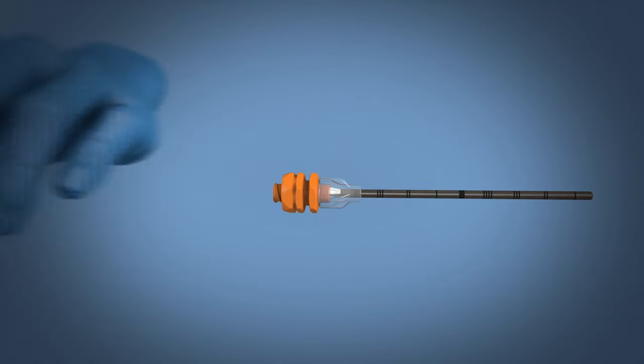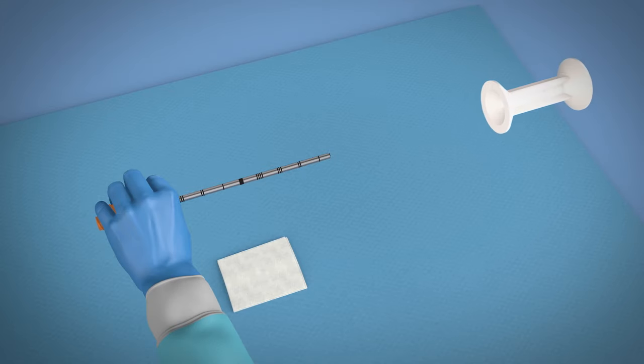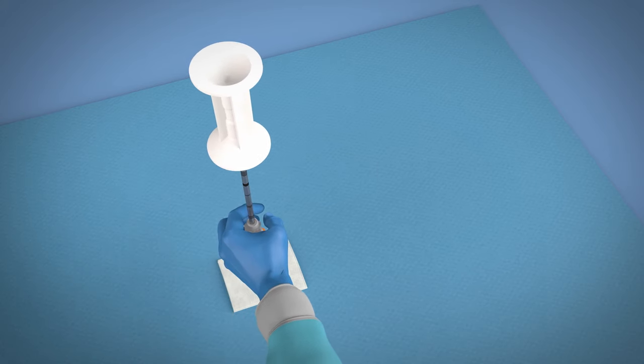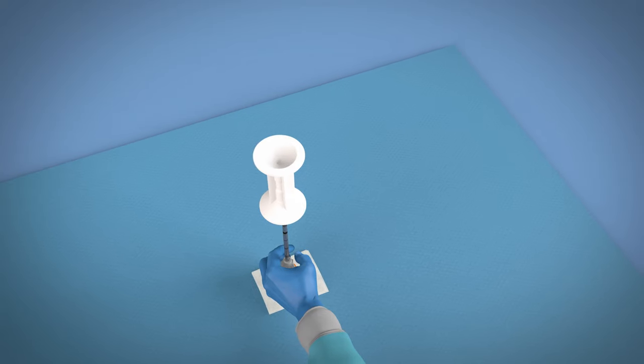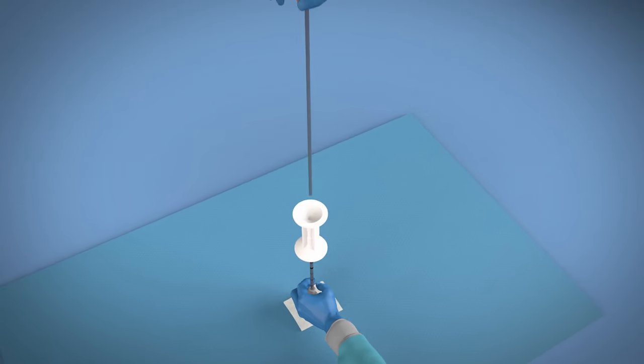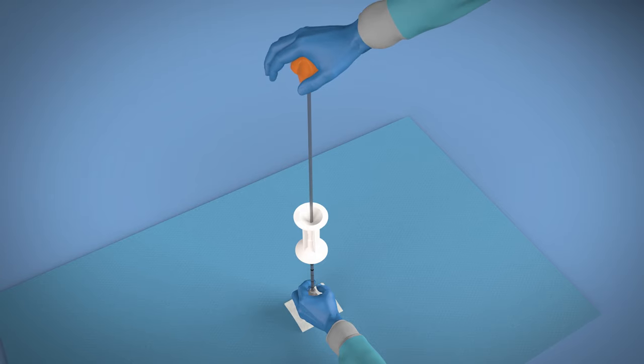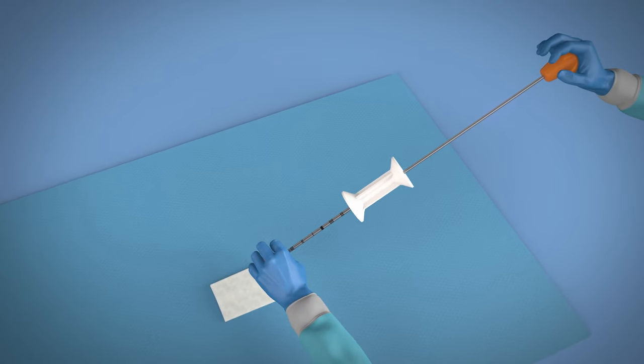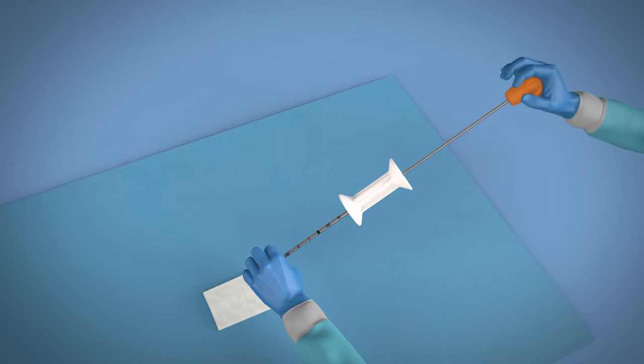Retract the black collar and remove the needle. Insert the tip of the cannula into the white alignment guide. Turn the cannula and alignment guide upside down with the needle hub placed on a flat secure surface. Insert the ejector rod into the other end of the alignment guide and gently tap on the rod end. Ensure needle hub is not touching any surface to avoid damaging the core sample. Slide the ejector rod down through the cannula, gently pushing the core sample out of the needle hub onto sterile gauze, specimen container, or slide.